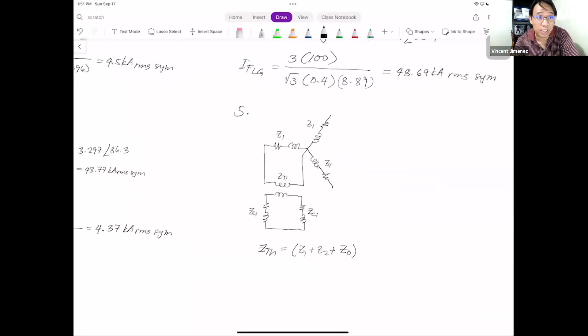Since the fault occurs at the secondary side of the single-phase system, it appears as if it's a line-to-ground fault, because line-to-neutral is our voltage. Except for the insertion of ZT1 and Z2, ZC1, it looks like a ground fault. That's why we need to get Z1, Z2, and Z0 of the system network, then add the impedance of transformer 1 and the two cable paths, ZC1 — that gives us the total Thevenin equivalent impedance as seen from the fault point.